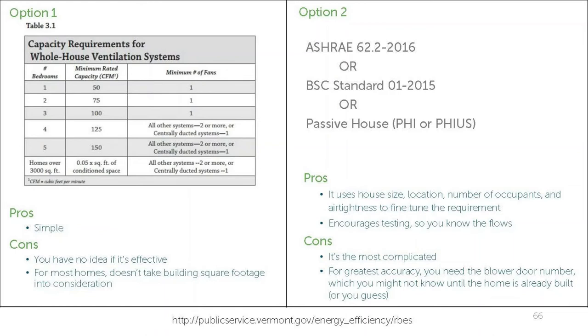There are two options for determining the size of the whole house ventilation system. Option 1 uses Table 3.1 provided in the code. This option is simple, but doesn't accurately account for the home size. Option 2 requires meeting ASHRAE 62.2-2016, Building Science Corporation Standard 1-2015, or Passive House Standards.